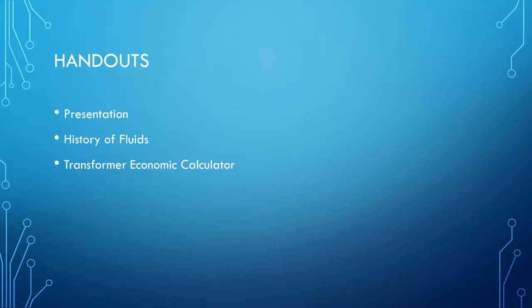That's a great point. And one of the handouts is the FM document that outlines the requirements. It's fairly simple. The transformer needs integral fusing or fusing upstream. It has to have a cover mounted pressure relief device, depending on the kVA size. And I believe it may have to have contacts on the pressure relief device if you get to a certain kVA. And obviously it must be filled with the higher fire point fluid.